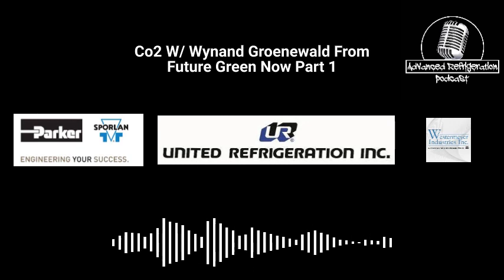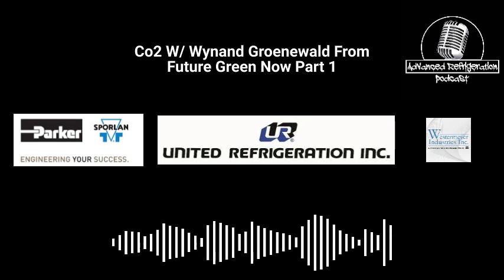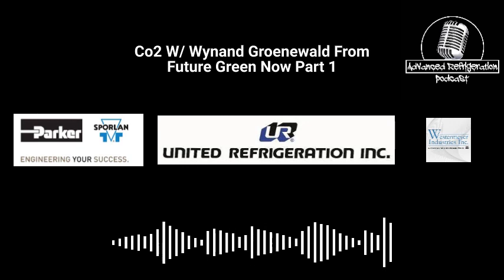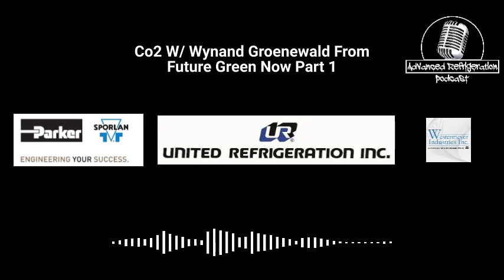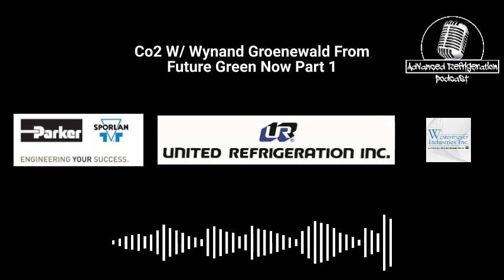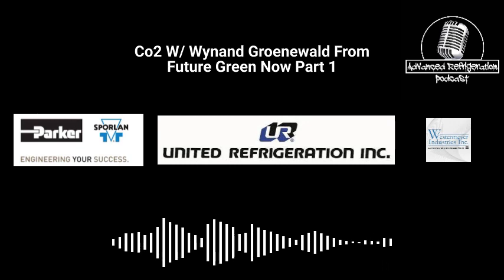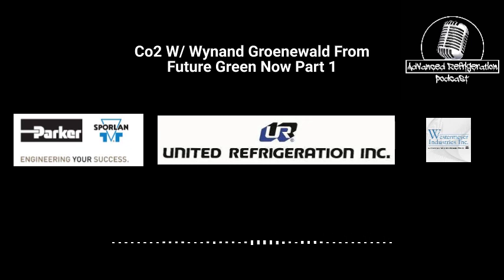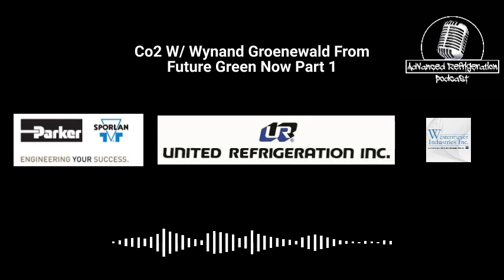And also, you're moving flash gas, so that's another thing you need to understand. The flash gas in a system is actually very interesting. That comes back to the high ambient strategies. Every high ambient strategy is based around taking care of the flash tank in the receiver. But one benefit, and it comes to the low side of life, is where CO2 really gets the benefit of having the flash tank, because flash gas is not a CO2 thing, it's any refrigerant. As soon as you have a pressure drop and you go into your two-phase region, you separate vapor from liquid.